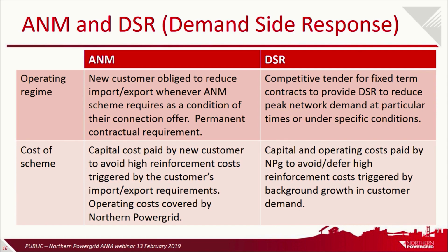We don't charge an ANM operating cost. There is an annual operating cost for us to run those schemes, but that's rolled into our normal operating costs. For demand side response, this is more about where the background level of demand on the network has grown over time. All our customers are operating within their agreed capacities, but they're using more of that agreed capacity over time, and we eventually reach a point where the potential overload isn't attributable to any single customer asking for more. Under those circumstances we need to solve that problem at our cost, going out for competitive tender for fixed-term contracts to provide some sort of DSR solution as and when that condition occurs.